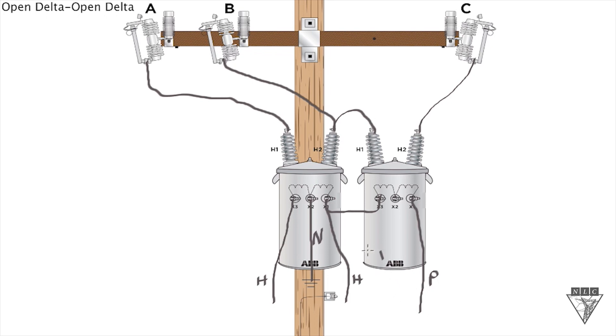That's an open delta, open delta connection. One thing to remember with an open connection, open delta, open delta connection, it's only 57.7 percent as efficient as a three transformer bank. So it is for lighter loads, lighter three phase loads.